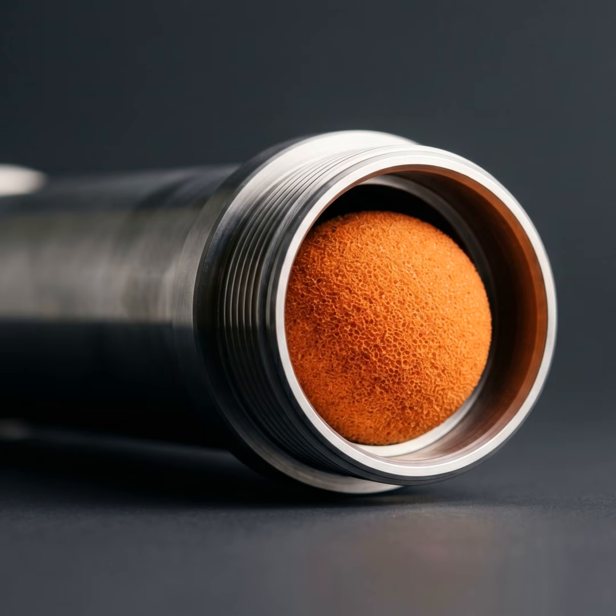But wait, I can hear the skepticism forming, and it is a valid engineering concern. Yes, because my immediate pushback when I read this was, wait a second, you are intentionally pumping thousands of sponge balls through a high-pressure, mission-critical industrial pipe. Sounds like a recipe for disaster. Right. Doesn't that just create a colossal clogging hazard? How do these sponges not just disintegrate under the pressure, turn into sludge, and completely ruin the water supply or break the chiller? It is the most common objection, and the sources address the mechanics beautifully.